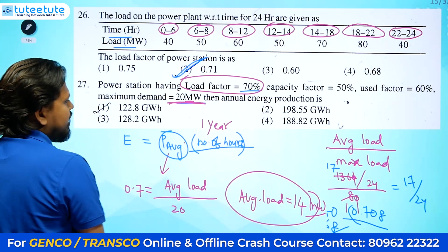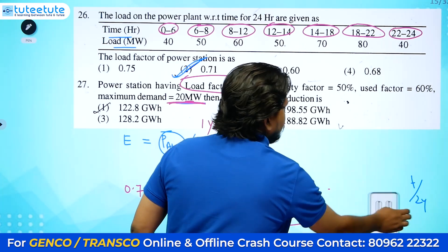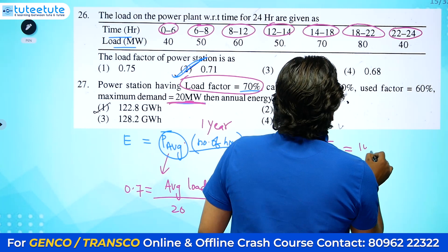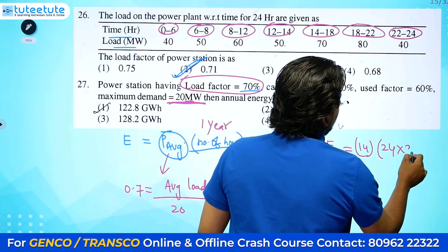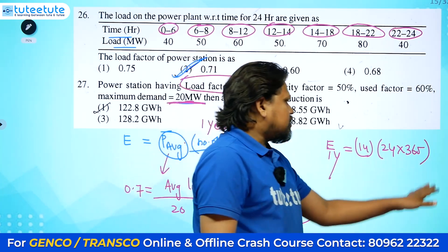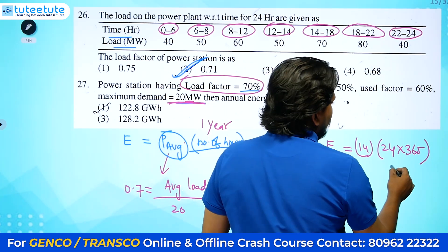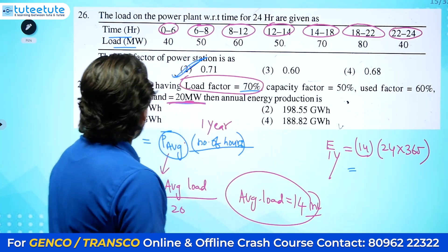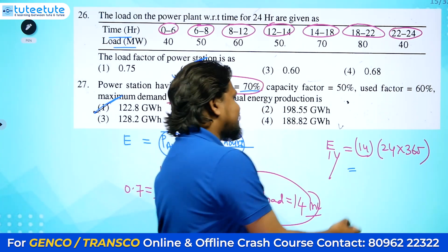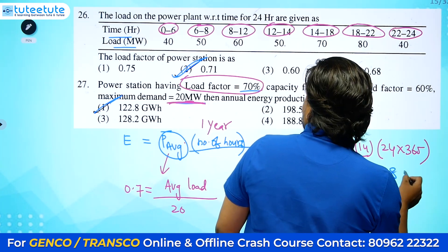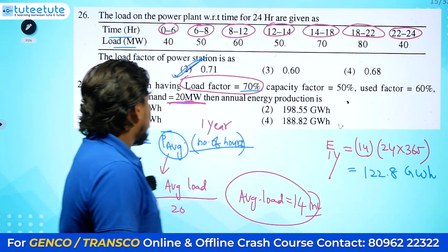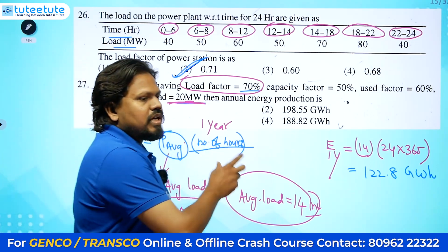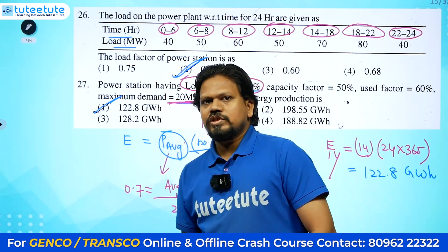Average load is 14 MW. Energy for one entire year = 14 × 24 × 365. The value 24 × 365 = 8760 hours. So annual energy = 14 × 8760 = 122.8 GWh. This is how you calculate annual energy production for any generator — knowing the load on it and calculating yearly generation.